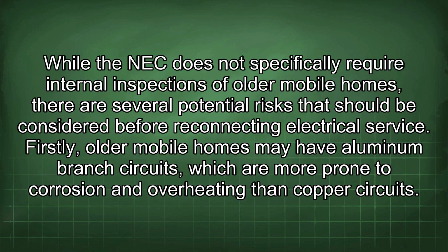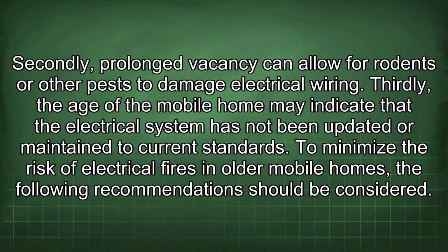While the NEC does not specifically require internal inspections of older mobile homes, there are several potential risks that should be considered before reconnecting electrical service. Firstly, older mobile homes may have aluminum branch circuits which are more prone to corrosion and overheating than copper circuits. Secondly, prolonged vacancy can allow for rodents or other pests to damage electrical wiring. Thirdly, the age of the mobile home may indicate that the electrical system has not been updated or maintained to current standards.